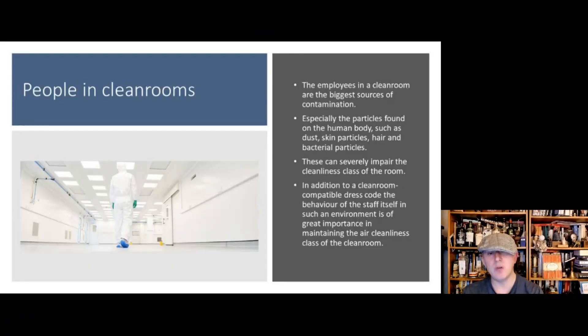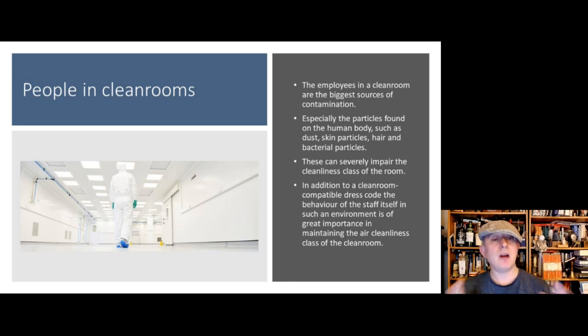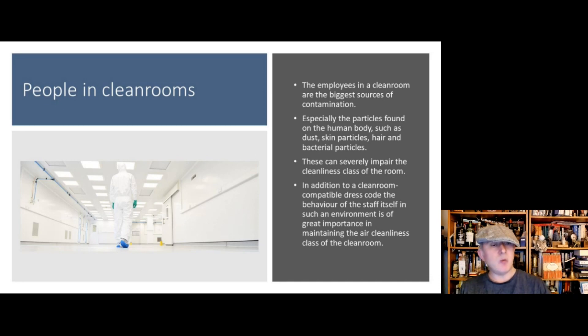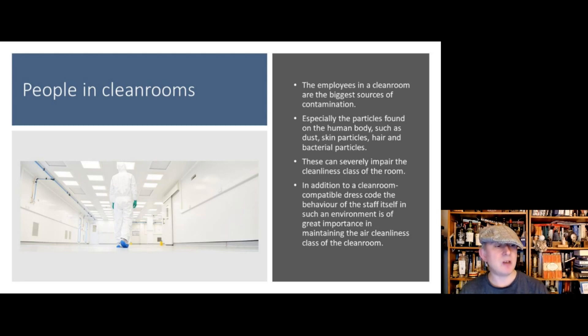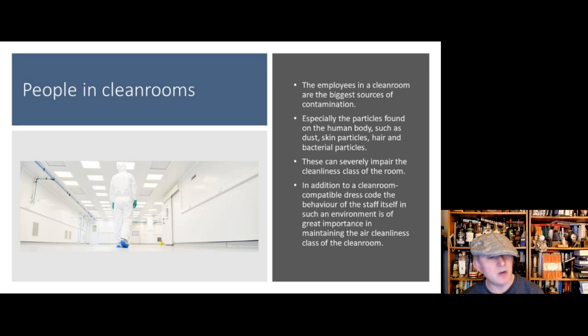Now we're going to look at people in clean rooms and key aspects of movement. People are the biggest source of contamination because of the generation of particles, some of which will be microbial. Those microorganisms are likely attached to rafts of skin matter, presenting a very severe contamination risk. Although we dress appropriately in clean room clothing, the movements and behaviors we undertake are of fundamental importance.